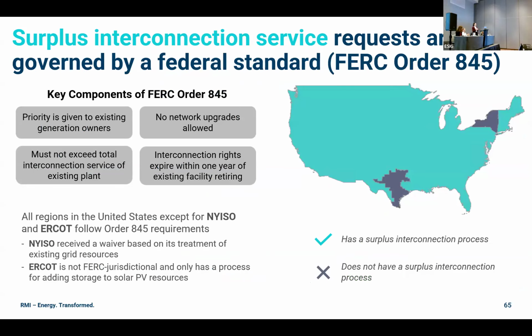First, a little bit more about surplus interconnection service. These are governed by a federal standard, FERC Order 845. You can see in this little map on the right that most of the US has a surplus interconnection process, unless you're in ERCOT or the New York ISO, which received a waiver. The key components of this service are that priority is given to the existing generation owners, there are no network upgrades allowed, and you must not exceed the total interconnection service of the existing plant. So if it's a 100 megawatt plant, you can't put a 200 megawatt solar farm in under surplus interconnection service. And if that facility retires, the interconnection rights of the surplus facility will also retire within 1 year of that facility retiring.